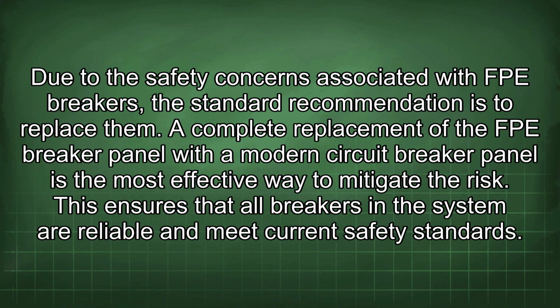Due to the safety concerns associated with FPE breakers, the standard recommendation is to replace them. A complete replacement of the FPE breaker panel with a modern circuit breaker panel is the most effective way to mitigate the risk. This ensures that all breakers in the system are reliable and meet current safety standards.